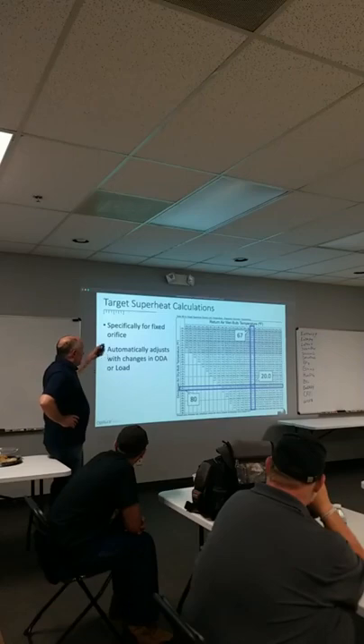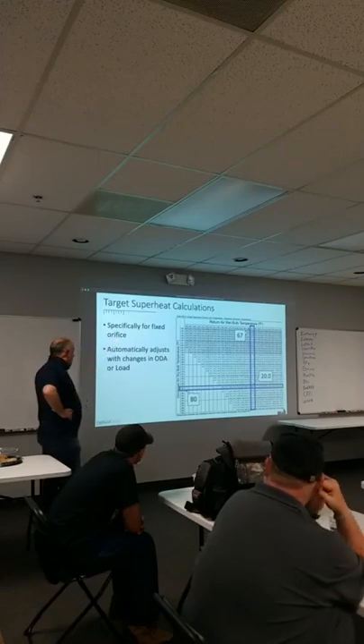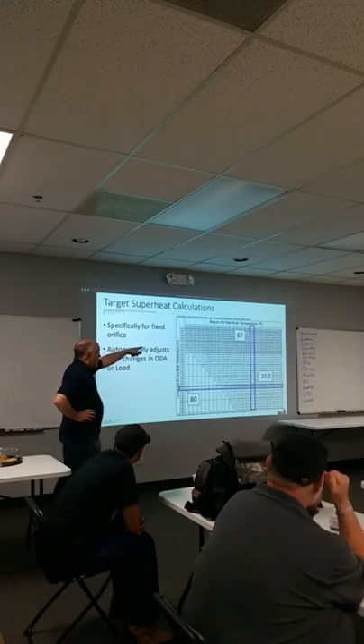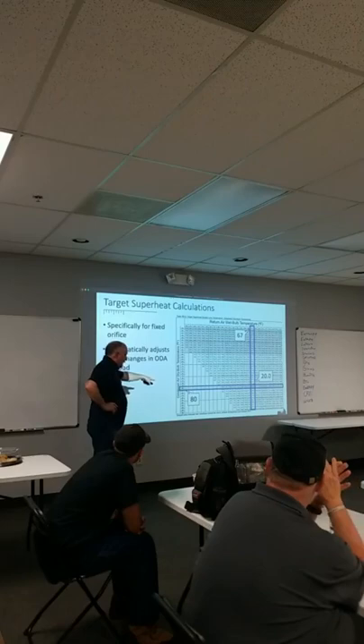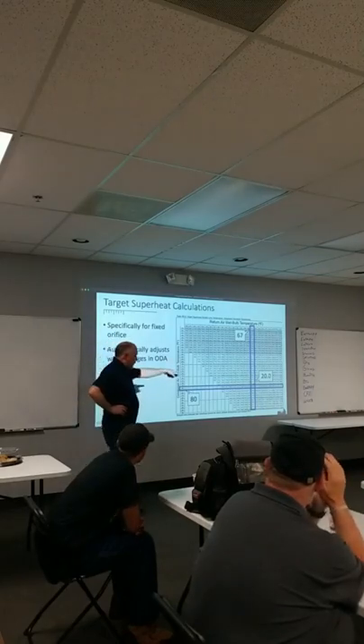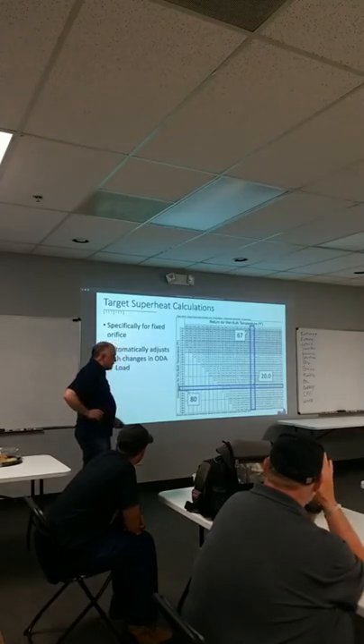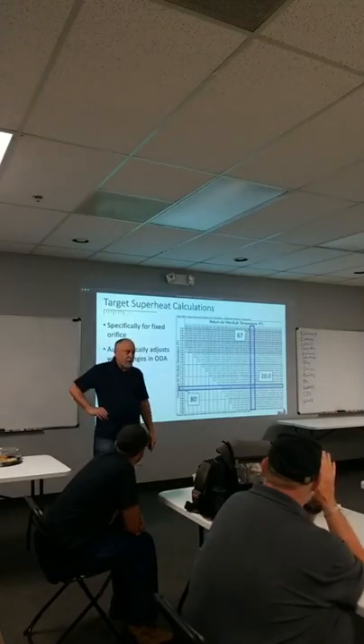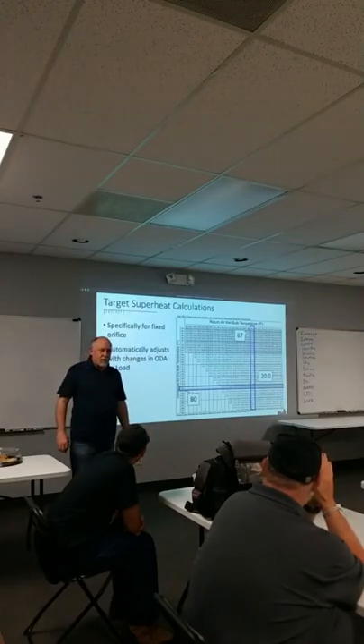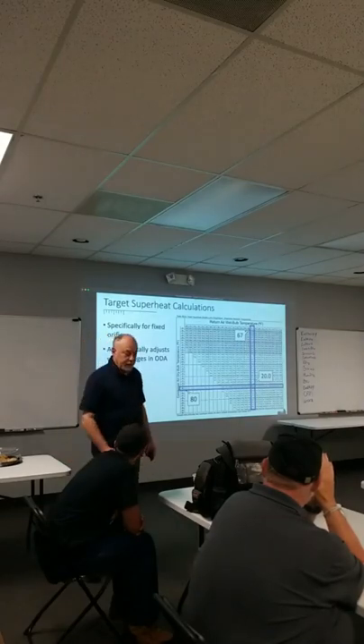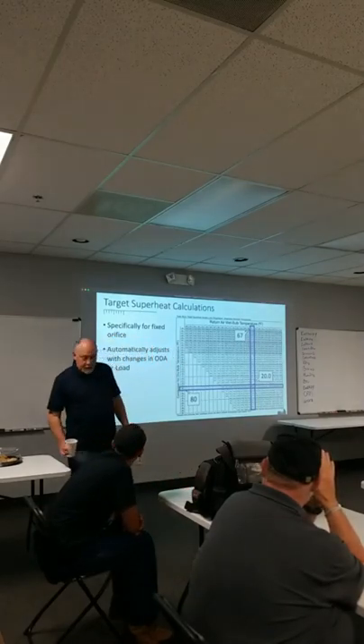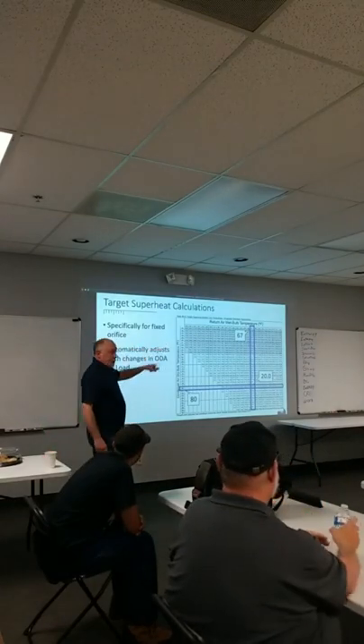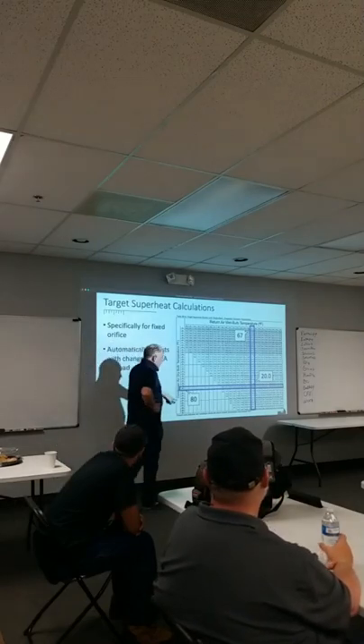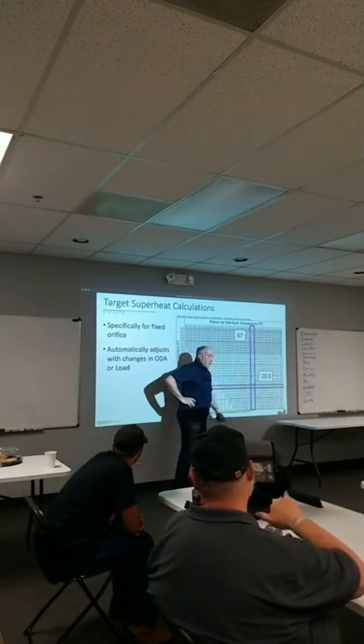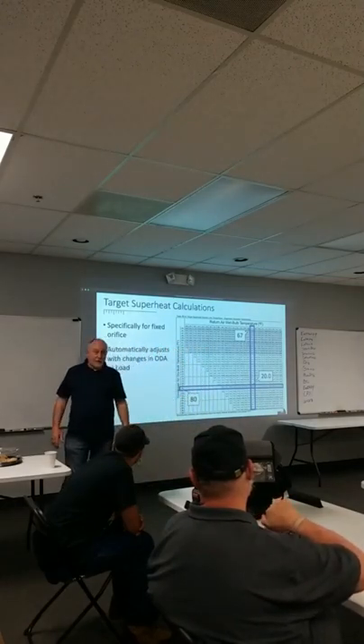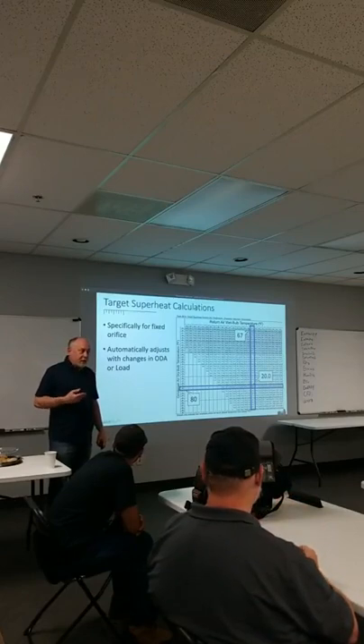Target superheat calculations for fixed orifice metering devices, specifically for fixed orifices. Let's say we have a return air wet bulb of 67 and a condenser dry bulb of 80, you're gonna get a target superheat, let's say at 20 degrees. Now what's interesting with this is this target is continually changing. As soon as you turn on your thermostat, what's the first thing in the room that starts to change? Humidity. You take your coffee, Jeremy, since it's mine. Right. All right, the humidity starts to drop, which means what else starts to drop? The wet bulb temperature, right. So as soon as we start that machine up, your superheat might go from 20 to 18 to 16 degrees over a course of 15 to 20 minutes. If you're not continually going in and getting a new wet bulb reading, you're not gonna get the charge correct.